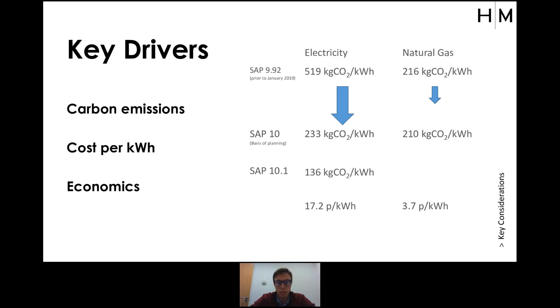So I was going to look at the characteristics of heat pumps, and this is a vast subject in itself, but some of the key points. Looking at different heat pumps, you've got a performance envelope to be careful of, and whether that works with your network design temperatures. Be it an air source heat pump, you've got to worry about minimum operating temperatures and then upper temperatures, and also things like delta Ts all go into impacting on the efficiency. Ken's selection tools and so on, I imagine will be very useful, and it'll be good to get a copy myself of that.